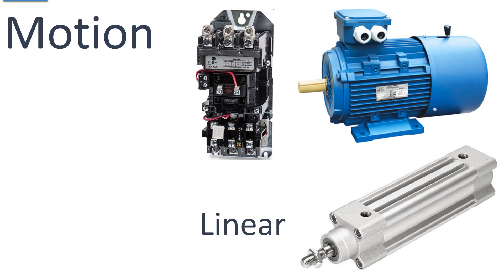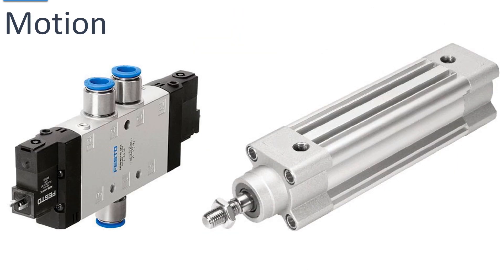Linear motion goes to either hydraulic or pneumatic cylinders. This is a pneumatic cylinder, and it uses a pneumatic solenoid valve. This valve has two solenoids on it, one on each end, and it electrically, by way of electromagnetic force, shifts a spool inside of the valve body to control the direction of the cylinder.